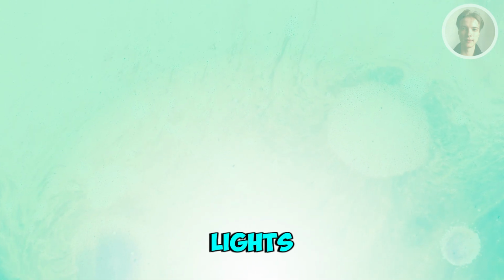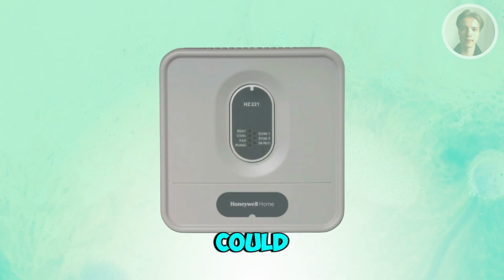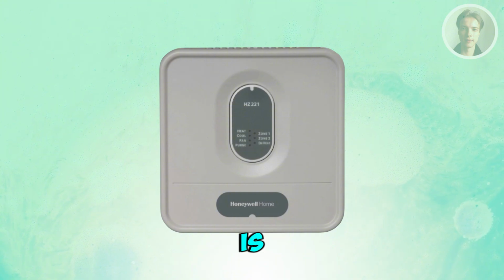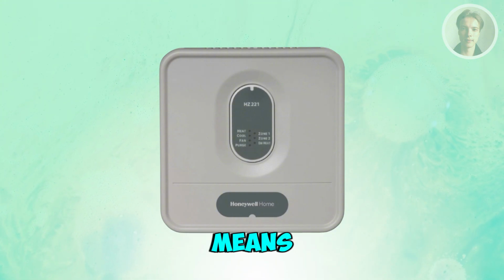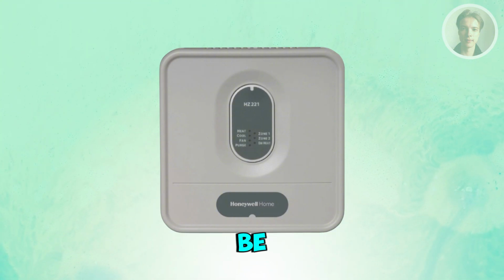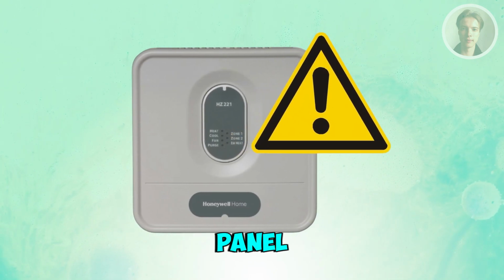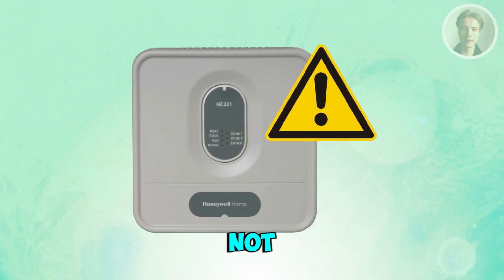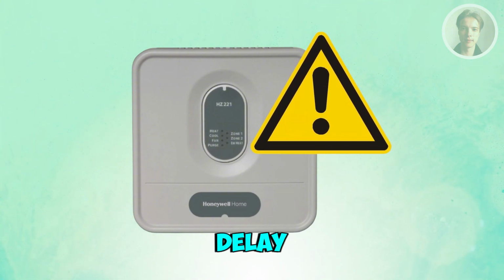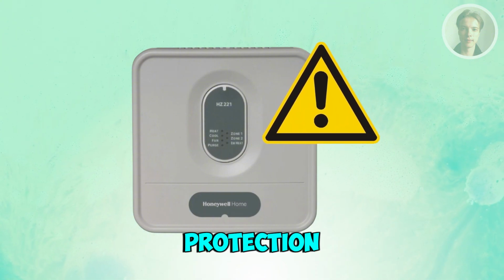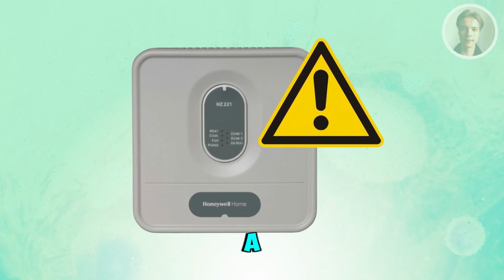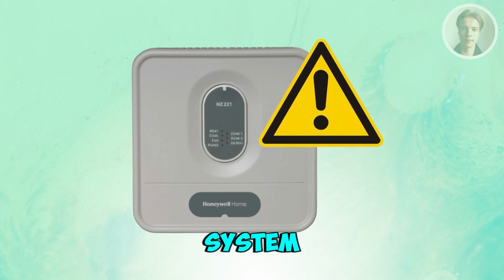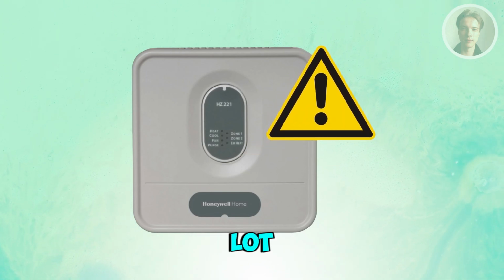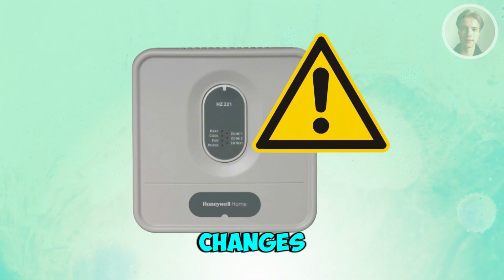So, if you're looking for a way to fix your Honeywell TrueZone panel lights if it's blinking on and off, well, there are a few things that you could actually do here. Now, first things first, you need to understand that blinking usually means the panel is waiting or may be stuck. So, when a TrueZone panel blinks on and off, it usually is not broken. It's often stuck in a delay, purge, or protection cycle, waiting for a safe condition before turning the system on. Now, this happens a lot after power loss or thermostat changes.